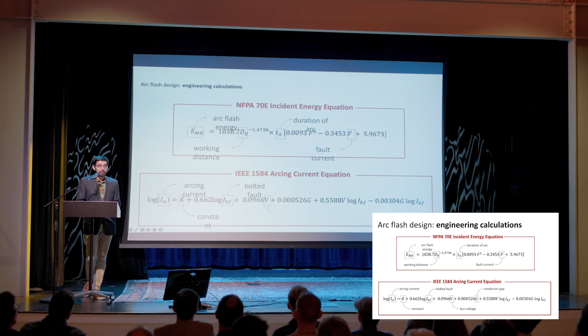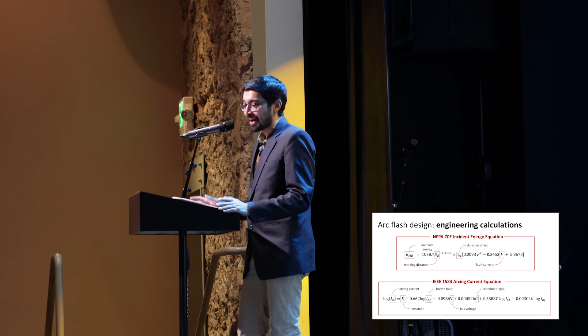So 2 equations are very important when conducting arc flash studies. One is the incident energy for NFPA 70E, and the other is arcing current from IEEE 1584. There's quite a lot of factors that go in here, so you can see how fast I made the switch from fun stuff to boring.